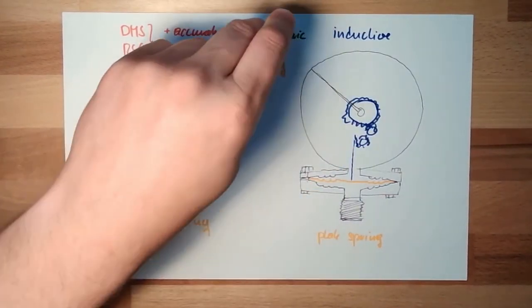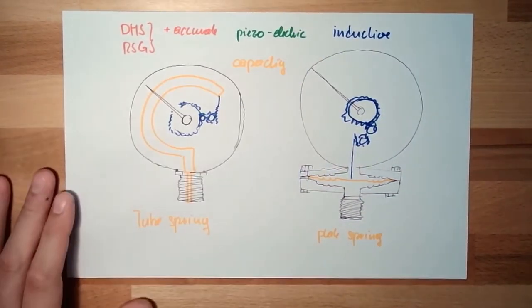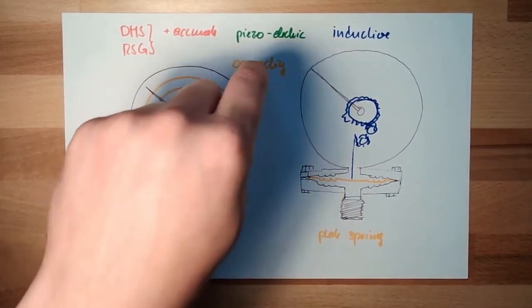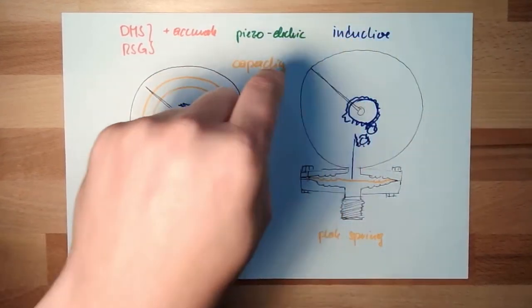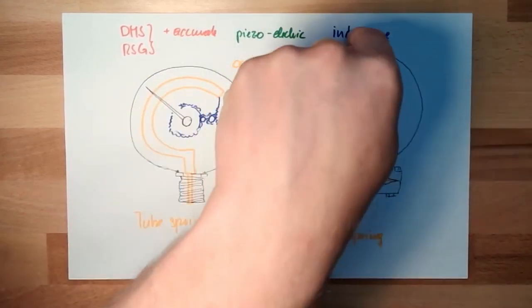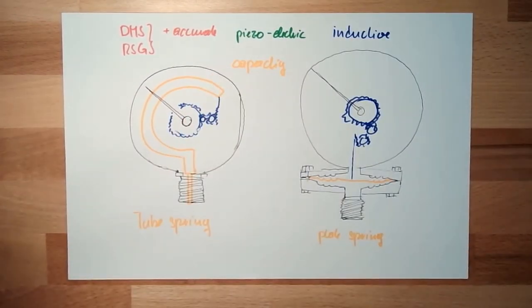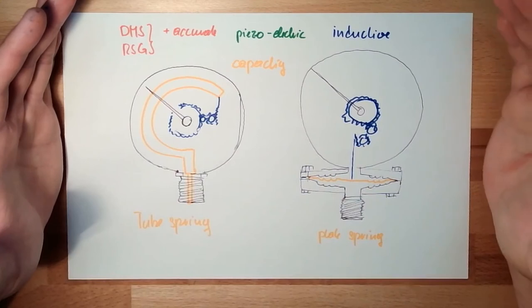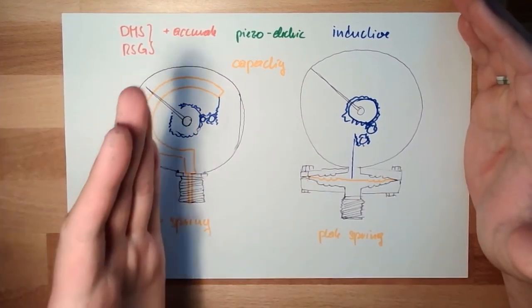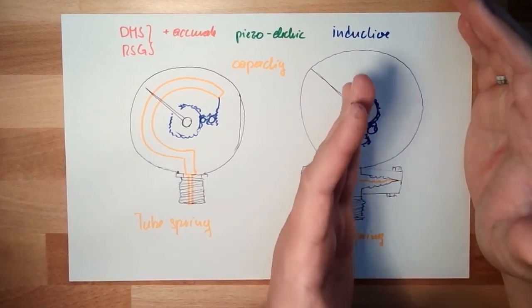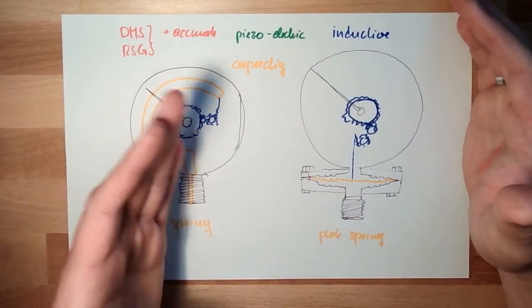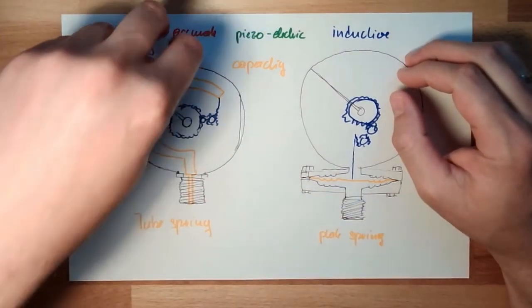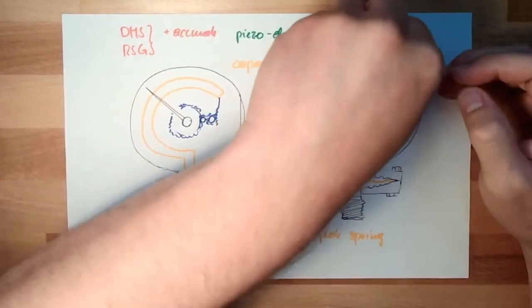The only thing which is really miniaturizable is the piezoelectric approach. Capacitive measurement is more dynamic than inductive, because with inductive you have to shift a higher mass inside the coil, while capacitive involves lower masses. So that's actually pressure measurement — the principle: some spring which is deformed, either tube spring or blade spring. Blade spring has more overload resistance than a tube spring. The movement can be measured with strain gauge, piezoelectric, inductive, or capacitive methods.